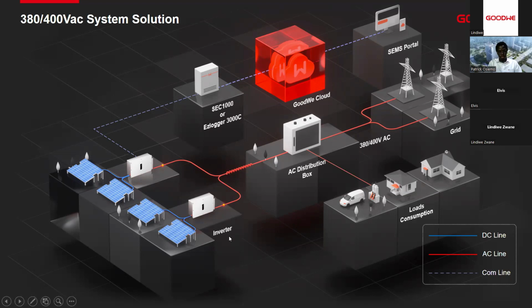On the communication side, we have our controller, either the SEC 1000 or the EZ Logger 3000C. Using the SEC 1000 or the EZ Logger 3000C, you are able to scale up the system to up to 60 inverters. Then from the controller, you're able to transmit data to our GoodWe cloud, and do your remote monitoring on our SEMS portal or SEMS app. Therefore, you can do remote monitoring on your phone, either Android or iOS, and also on your laptop.